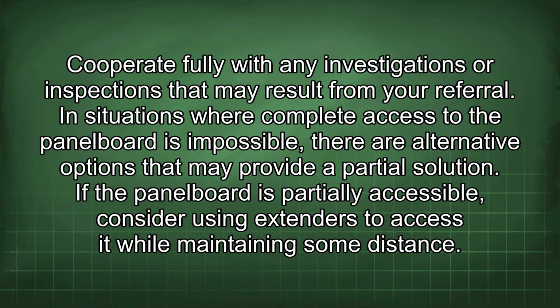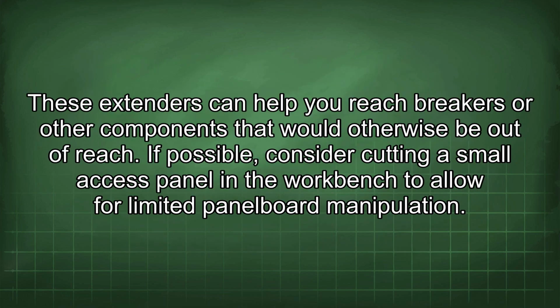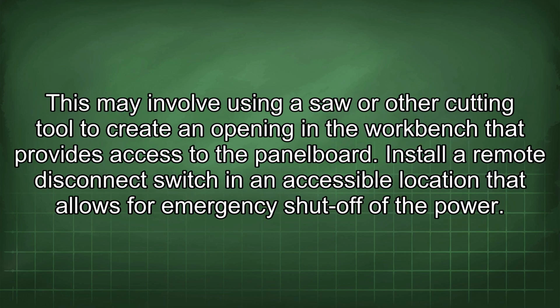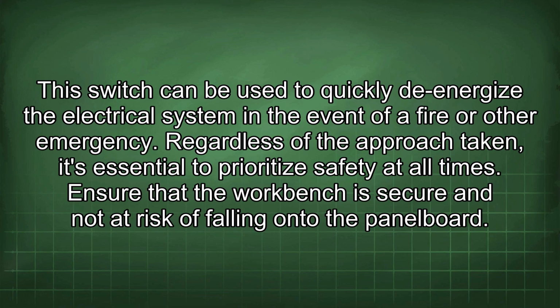In situations where complete access to the panelboard is impossible, there are alternative options that may provide a partial solution. If the panelboard is partially accessible, consider using extenders to access it while maintaining some distance. These extenders can help you reach breakers or other components that would otherwise be out of reach. If possible, consider cutting a small access panel in the workbench to allow for limited panelboard manipulation. This may involve using a saw or other cutting tool to create an opening in the workbench that provides access to the panelboard. Install a remote disconnect switch in an accessible location that allows for emergency shut-off of the power. This switch can be used to quickly de-energize the electrical system in the event of a fire or other emergency.